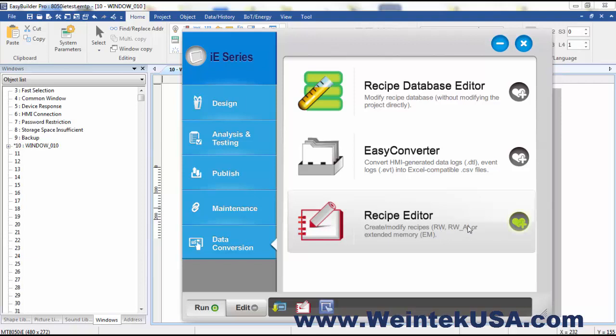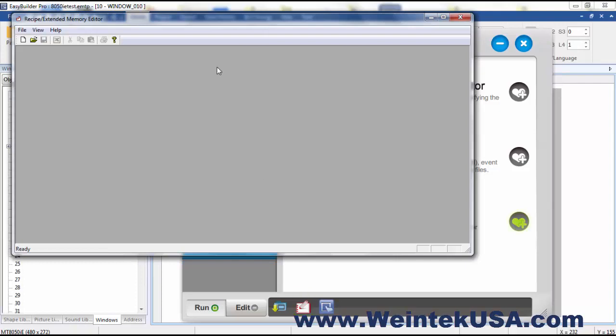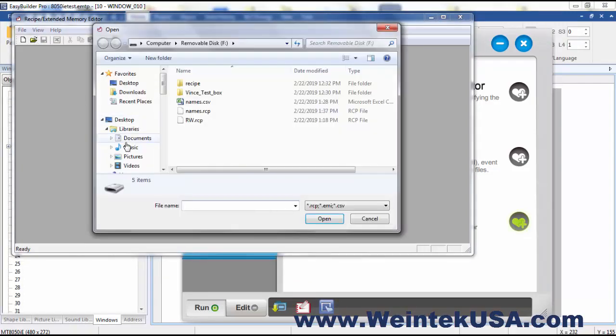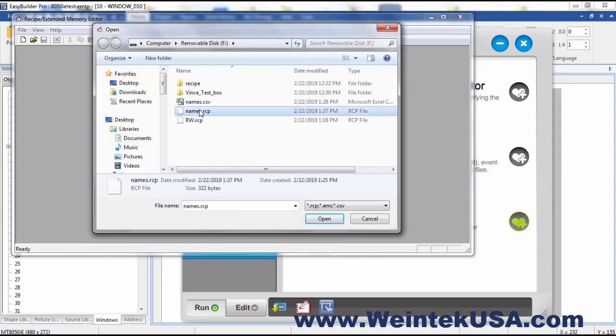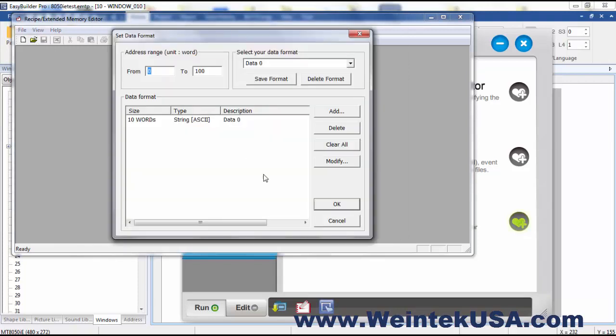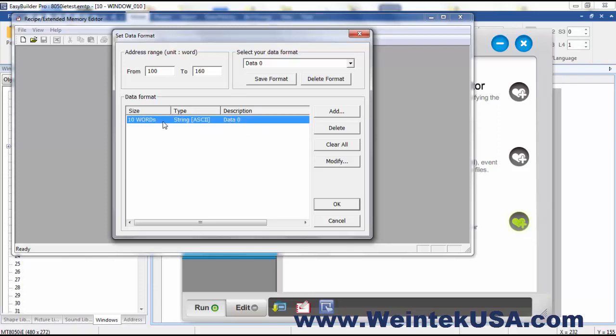Here you can actually create recipes in the sense that you can define data to be stored in retentive memory. It should probably more properly be called a retentive memory editor. You can also create extended memory files for your project. Here I'm going to go ahead and open up one that I already made. And in this particular case the memory we're using is register 100 to I think about 160.